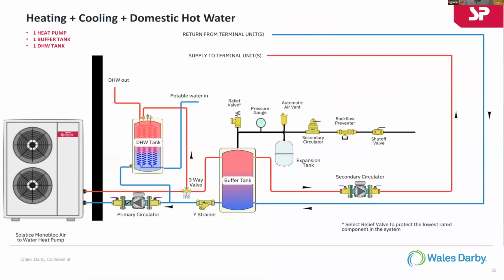Okay. Now this would be the setup where you're using it for your domestic hot water. So what happens is the unit will turn on and there's a three-way valve that sends the hot water directly to the tank to make domestic hot water. Again, you kind of have the same issues that you have with existing heat pump hot water heaters. You've only got 130-degree water to try and make domestic. So unfortunately, you're trying to bring cold water from 50 degrees up to 90 something degrees. It doesn't take a lot of BTUs. It just takes a great difference in temperature to do it.